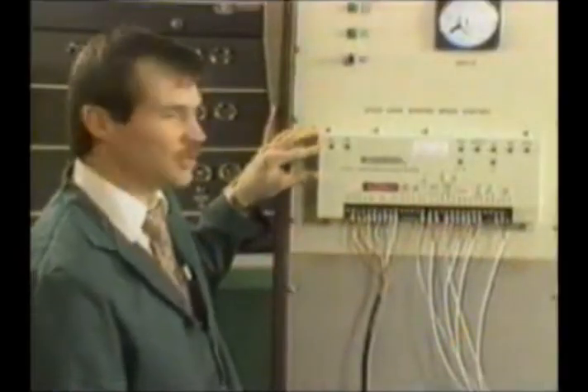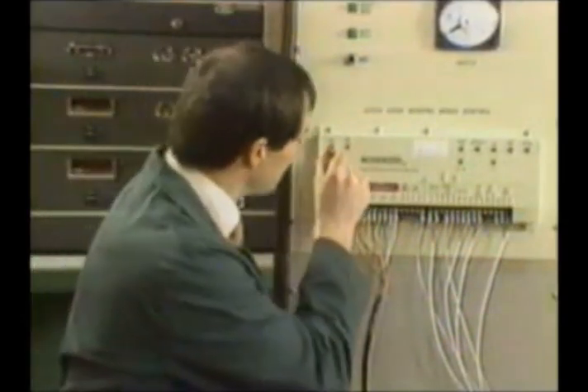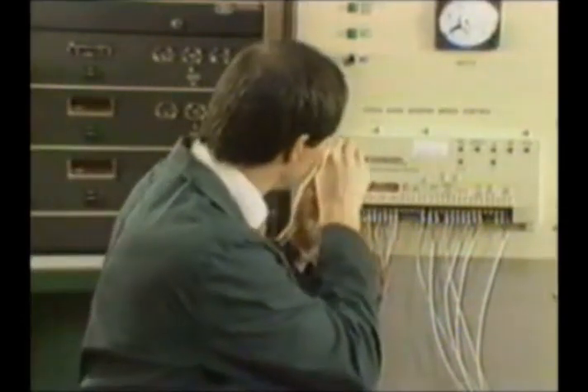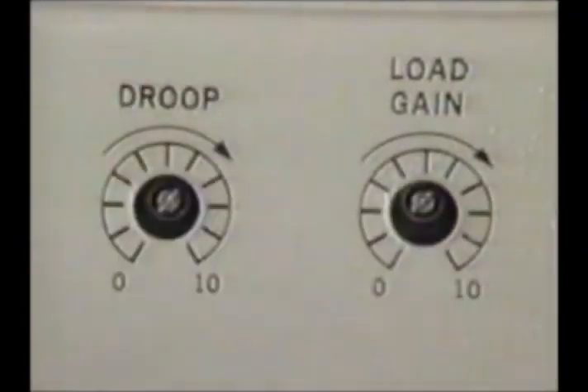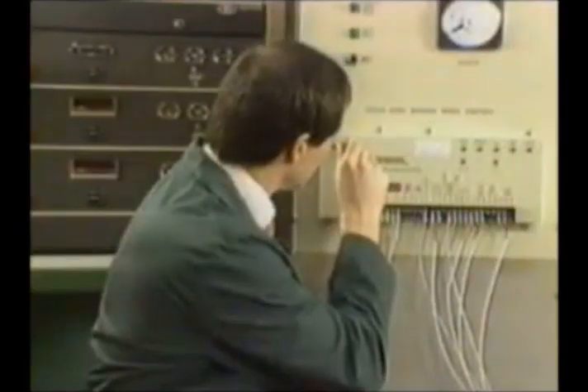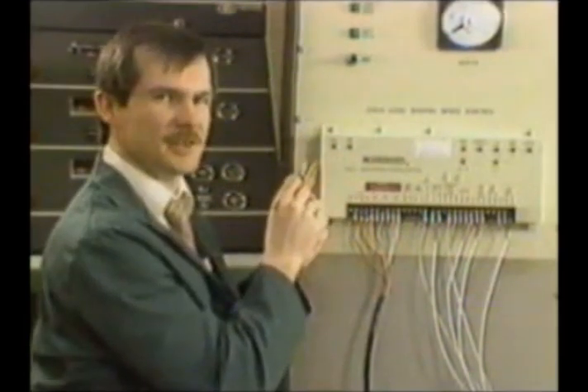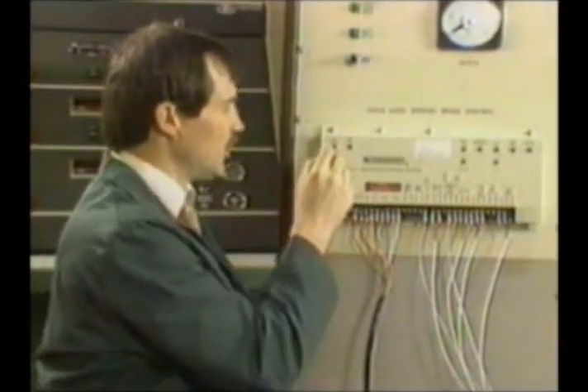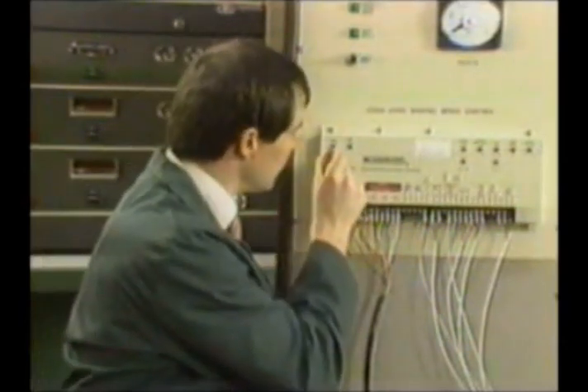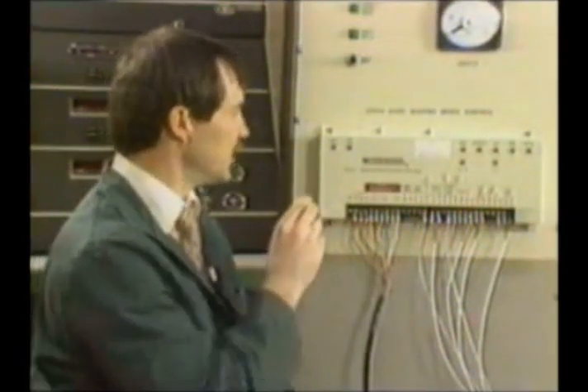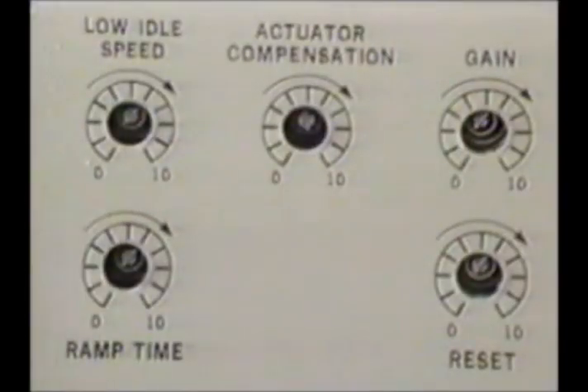We're going to start by presetting the droop potentiometer. I want to set my droop potentiometer full counterclockwise. My load gain potentiometer I want set at mid-range. Now you can see these pots are recessed underneath the cover of the control. And that's for when you use your screwdriver or tweaker, you're going to touch the side and that will discharge any static you have on your tool to make sure you don't static a component through the potentiometer. And that's why these are recessed, not just to make them harder to get to. On each dial here, I want you to notice they're labeled 0 to 10. So that should help you in your setups of them.